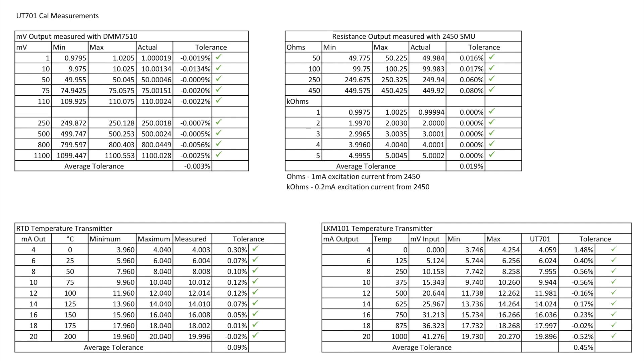Going down into the bottom there, there's my two temperature transmitters test results there. And again, everything is within tolerance. Our RTD is very good, 0.09 percent. That's way better than I would have expected really, especially with that type of transmitter. And the LKM 101, that's the thermocouple transmitter there. And again, everything is pretty good there. It's just that reading at the four milliamp level with zero degrees going in, 1.48 percent. That's the worst value across all the tables there really, but it's still within tolerance specified by the manufacturer. So all seems good at this moment in time.